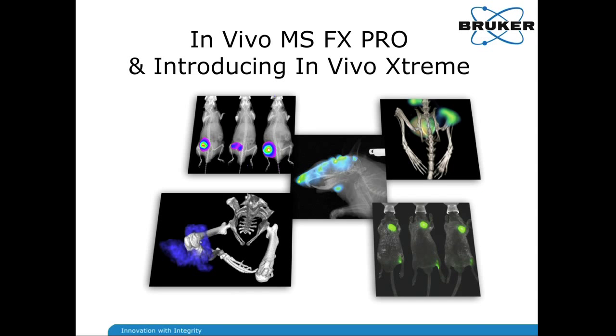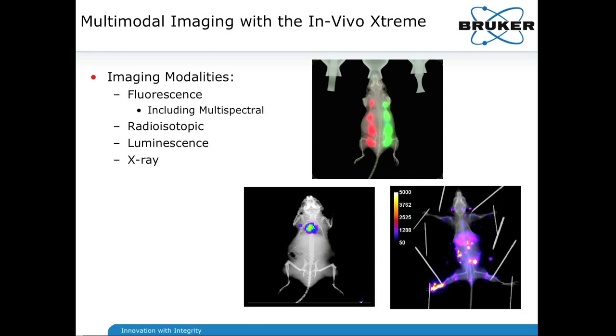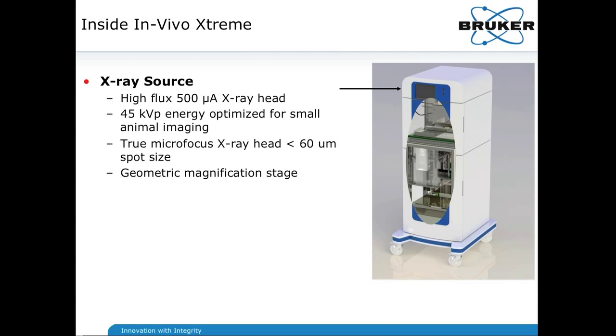We're going to switch gears now and focus on the In Vivo Extreme. As I mentioned at the outset, it allows for four imaging modalities: fluorescence, including a multispectral multiple-excitation analysis technique; radioisotopic imaging; luminescence; and x-ray. Up at the top we have an x-ray head, which is a 500 microamp x-ray source with a 45 kVp energy level and a true micro-focus, which prevents penumbra effect — giving you very good resolution of your x-ray throughout the imaging region.